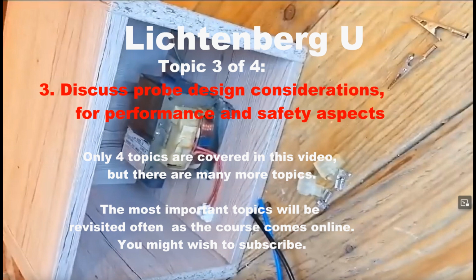Now, more about this one - these alligator clips as a probe type. Oh man, those heavy leads are completely a waste of time because this typically is less than an amp. 2,000 volts output at an amp is 2,000 watts of power being applied, which is quite a bit of power, depending on the current limiting on the input of your transformer and so forth. I'm going off a little too far here describing the amount of power involved, but certainly this type of lead is not a good choice.